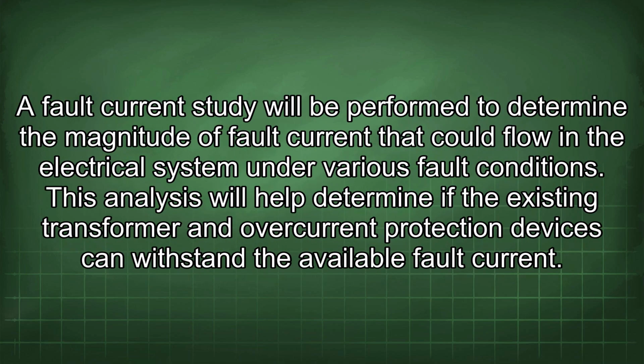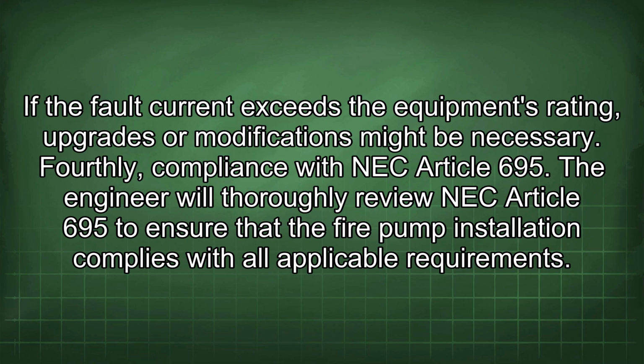Thirdly, fault current analysis. A fault current study will be performed to determine the magnitude of fault current that could flow in the electrical system under various fault conditions. This analysis will help determine if the existing transformer and overcurrent protection devices can withstand the available fault current. If the fault current exceeds the equipment's rating, upgrades or modifications might be necessary.